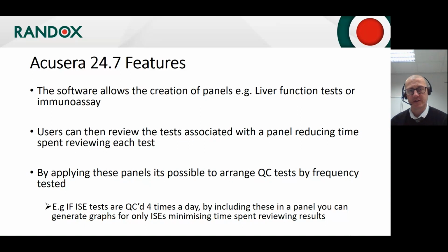You can also arrange these panels into tests by frequency. So for example, if you're running your ISEs and you need to QC them 4 times a day, then you could just make up an ISE panel. And then when it comes to reviewing these graphs, you would just have your ISE analytes, such as sodium, potassium, chloride. So again, this saves time, because instead of having to pull through data from 60, 70 tests to make a graph, you just pull in your 3 that you need, which minimizes the time that you're actually spending reviewing your QC results.